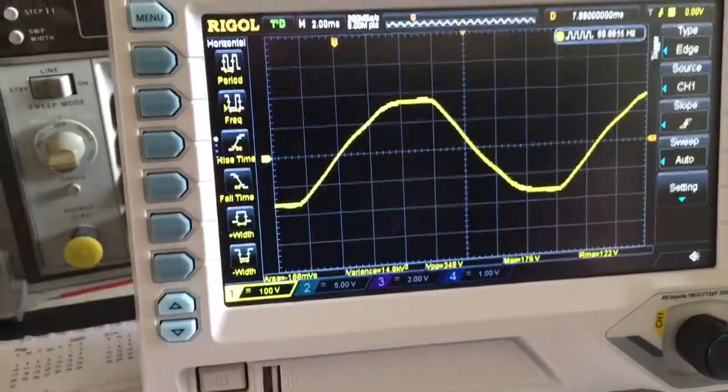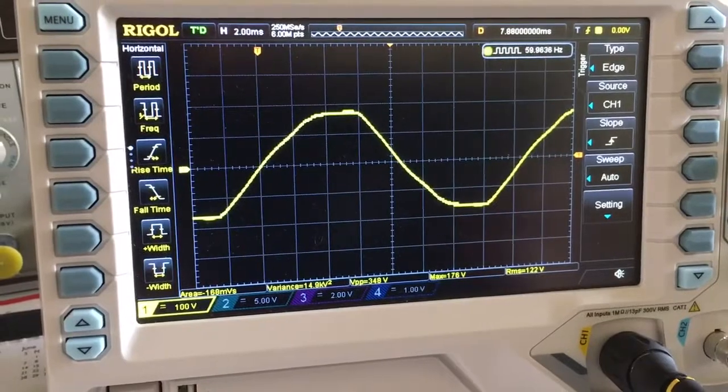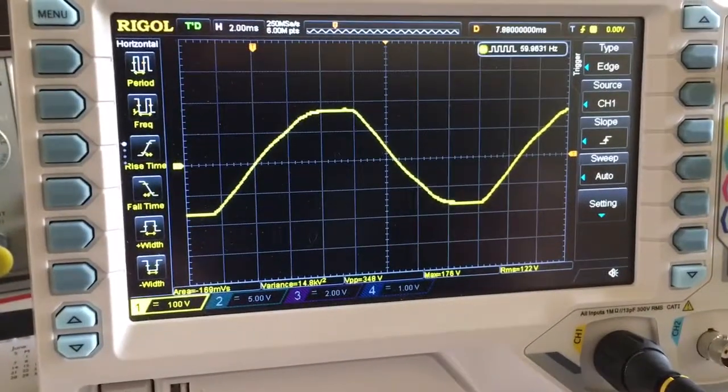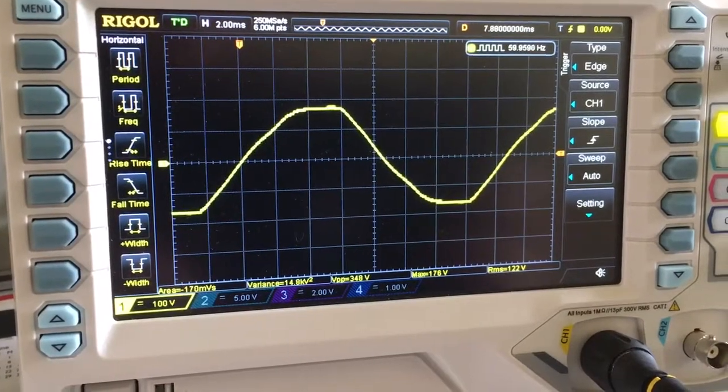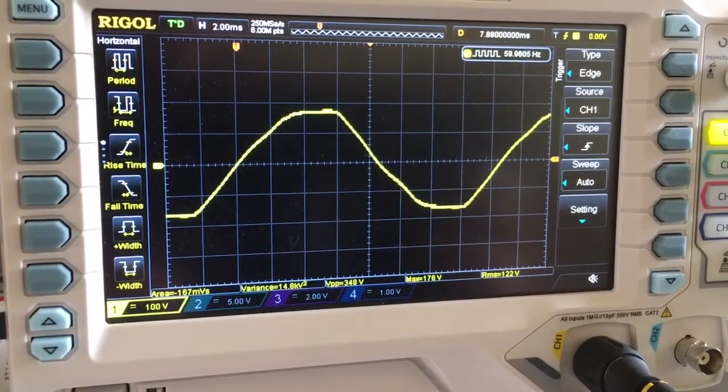Now, my meter hasn't responded back yet, so we're not seeing anything. Any meters that answer back would do that with very small glitches, 40 degrees from the zero crossings. But these modulations that you see here and here from time to time are, in fact, communications from the substation outbound.